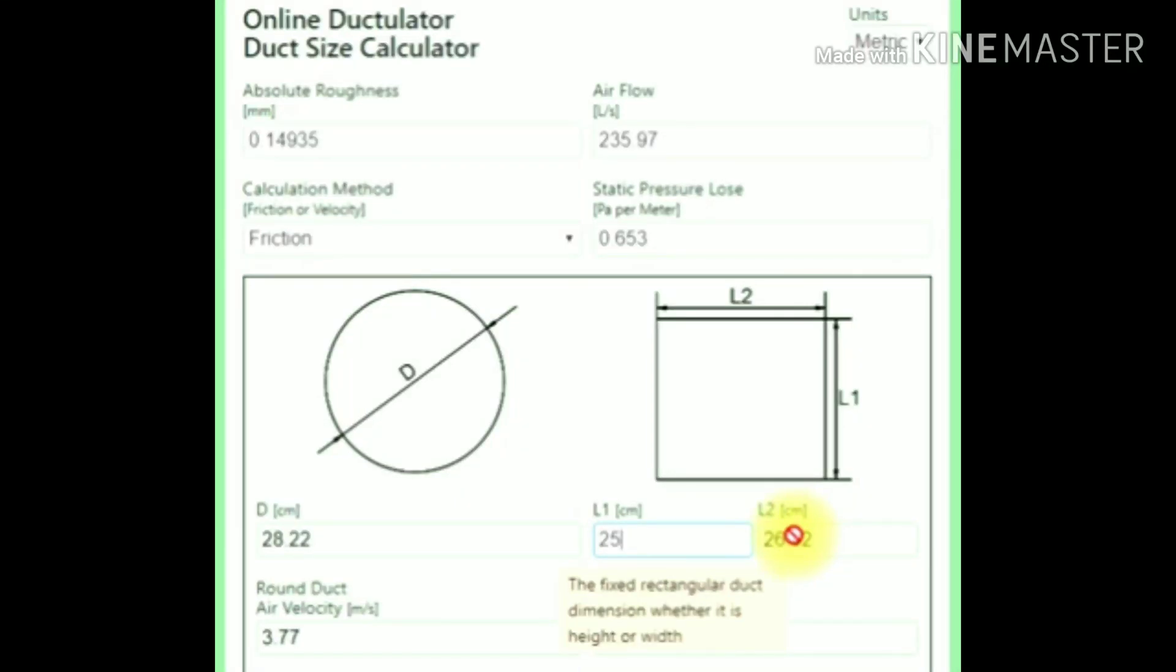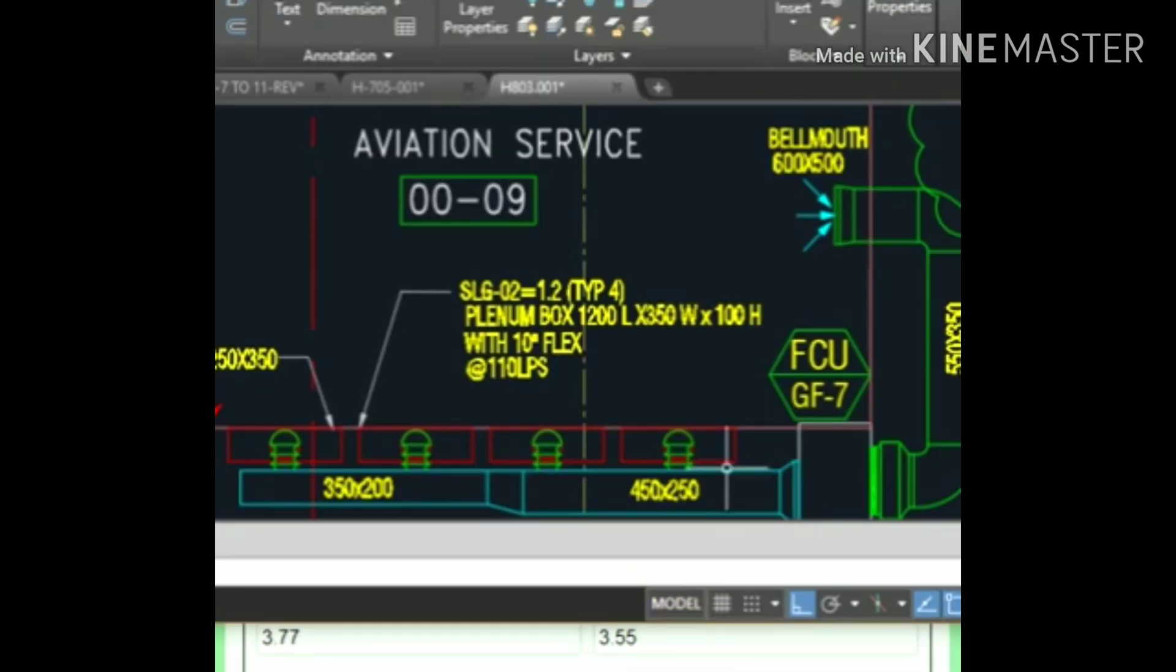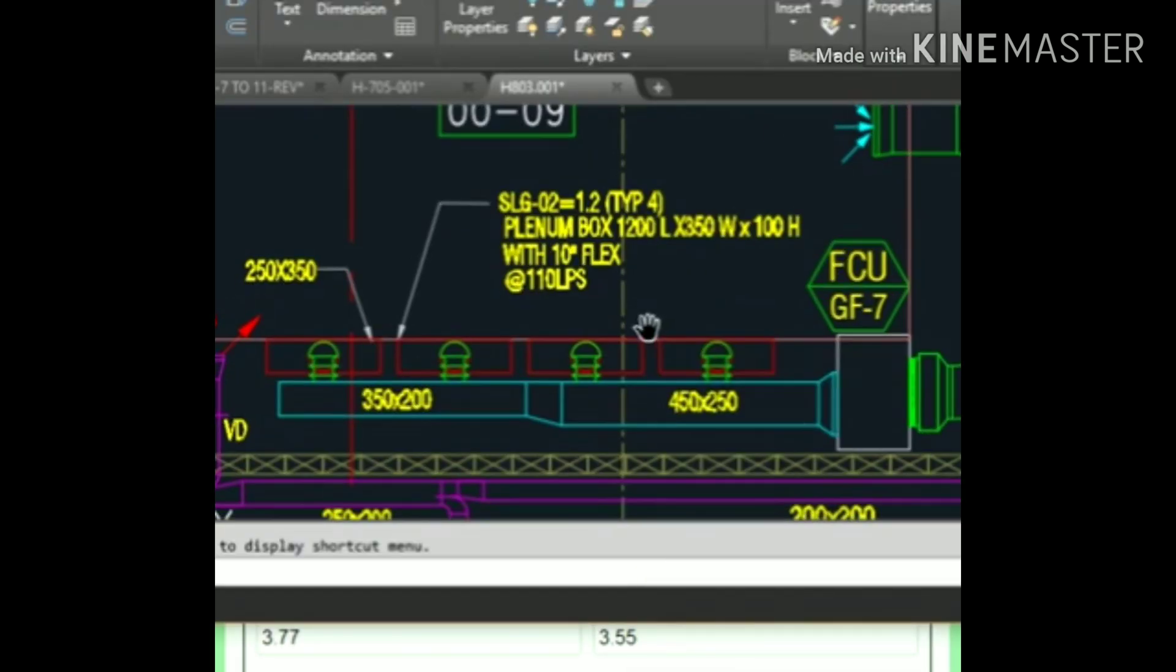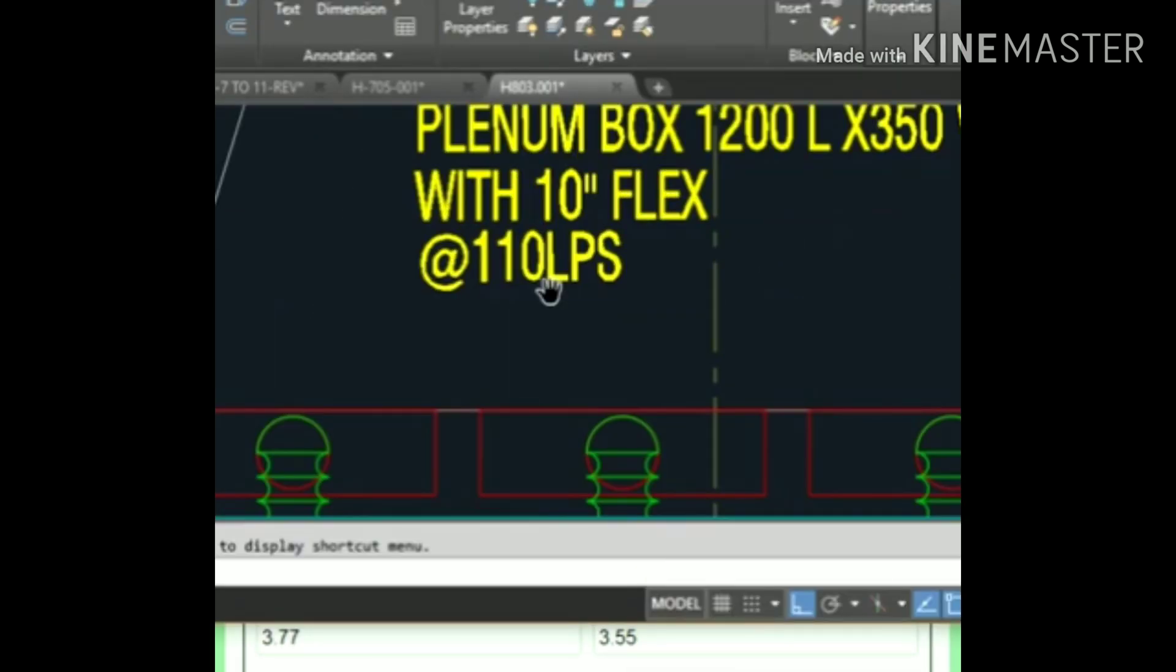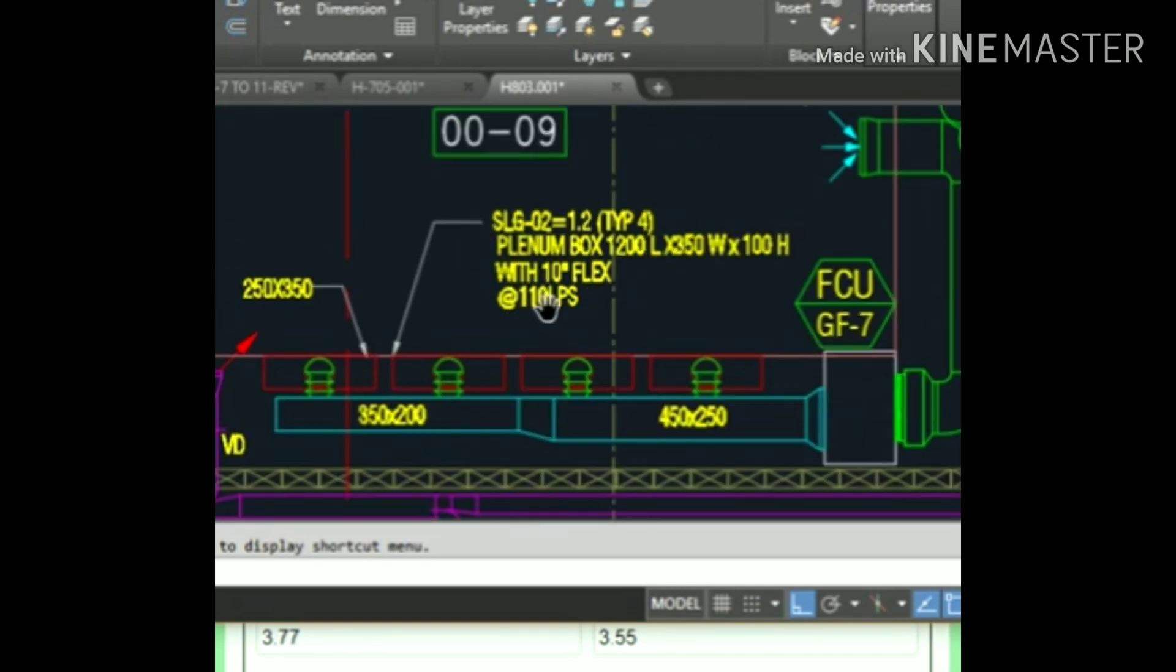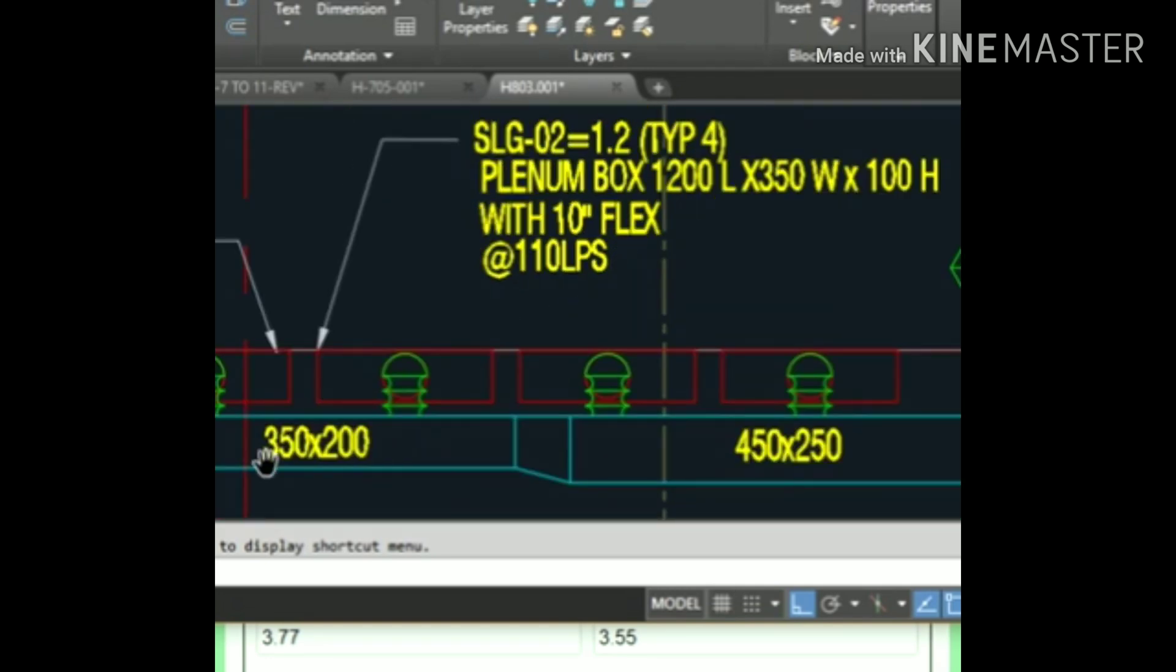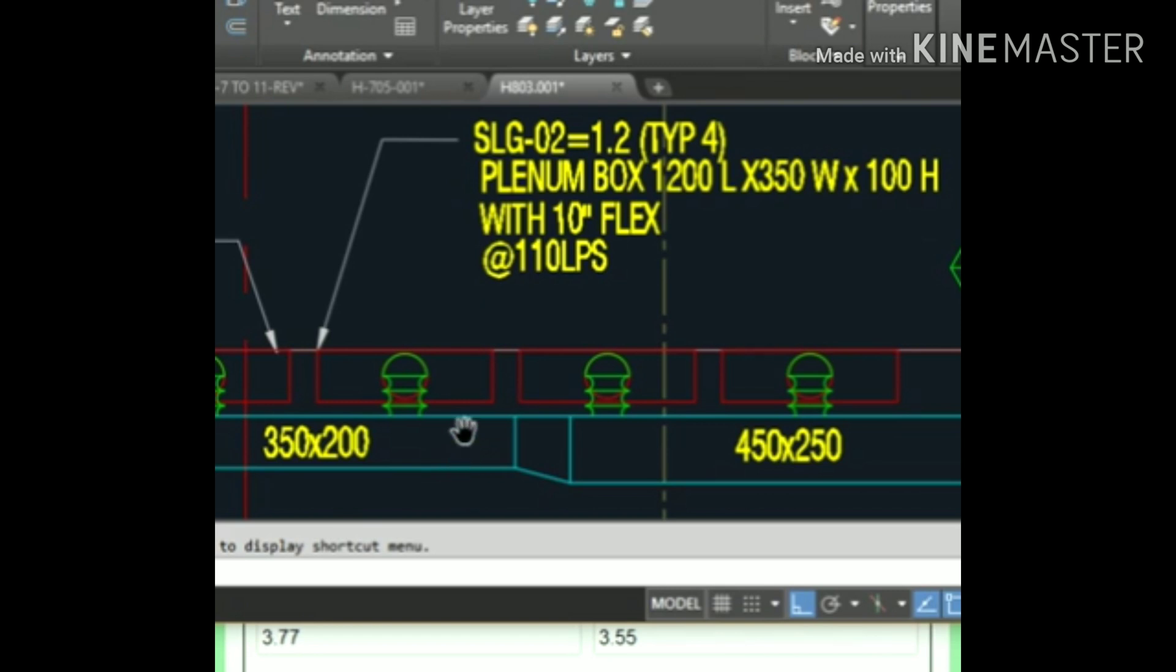I will be showing how to use an online duct calculator. The link is provided in the description box. For example, I have this drawing here. This is 110 liters per second. This is a reduced duct, so 110 liters per second on each branch means a total of 220 liters per second.